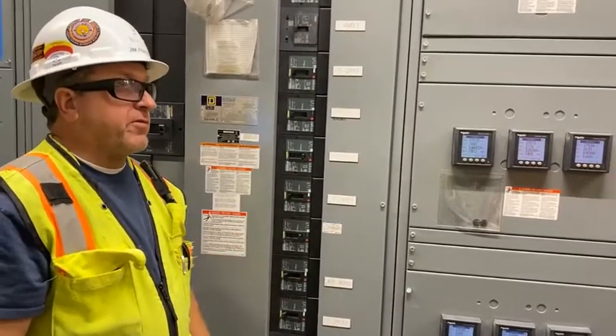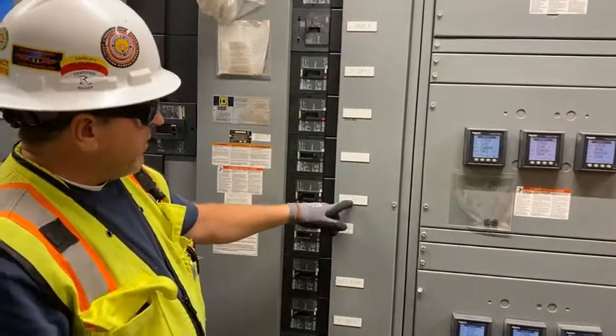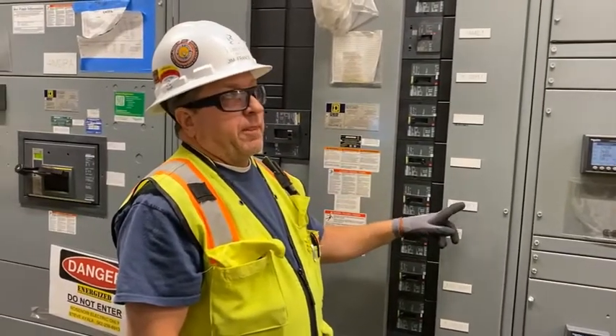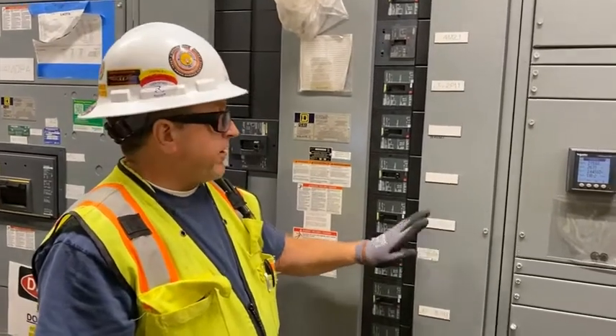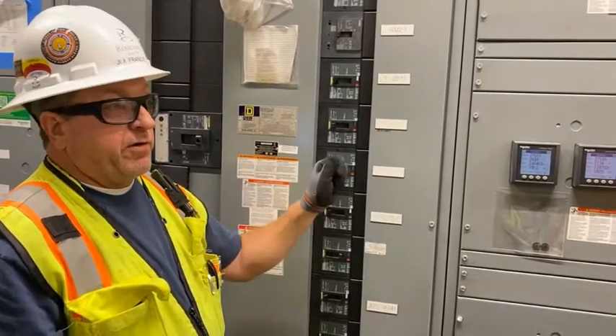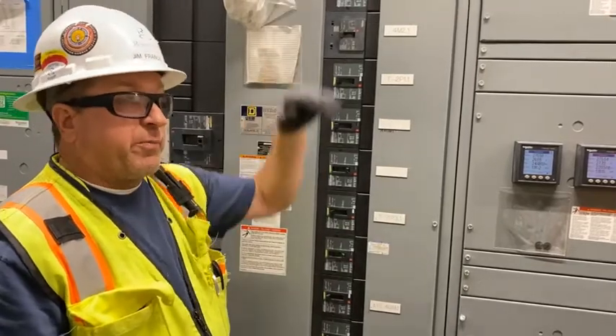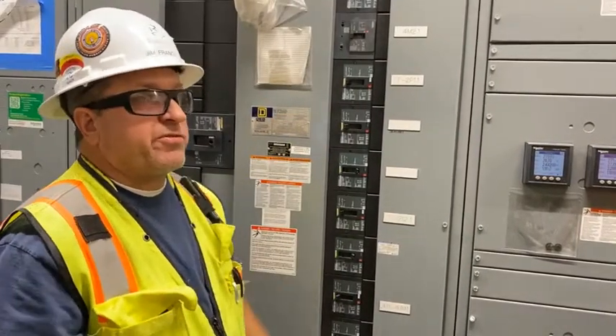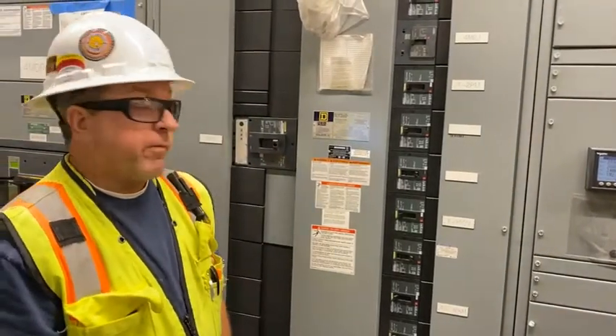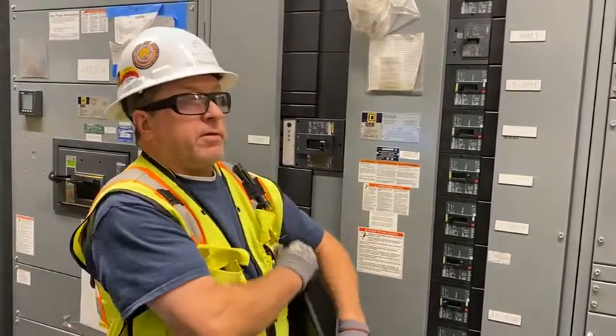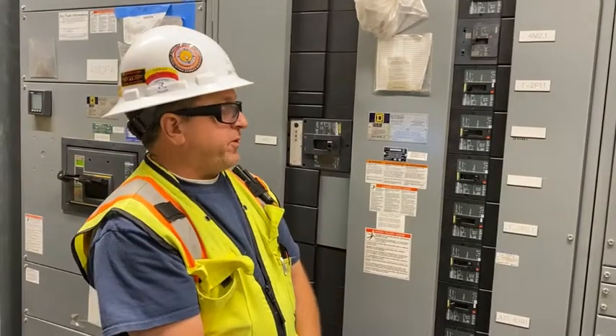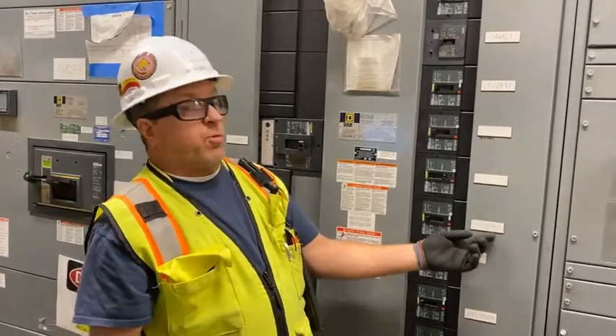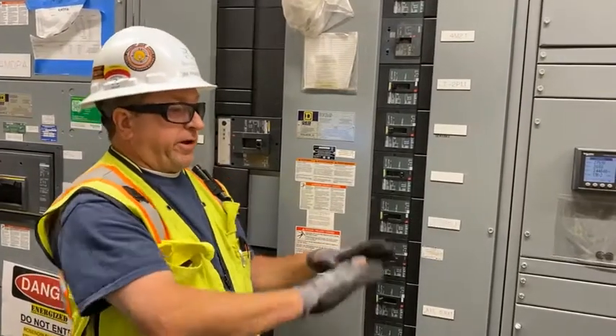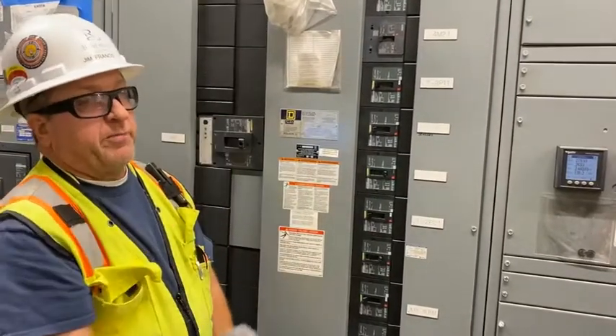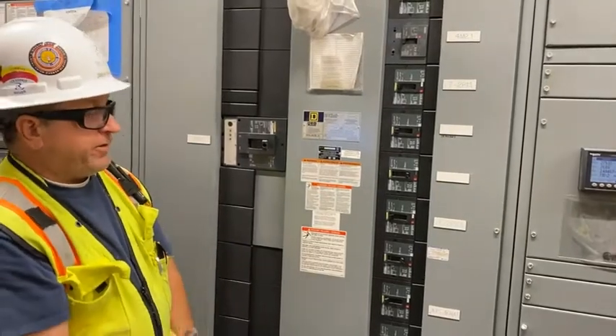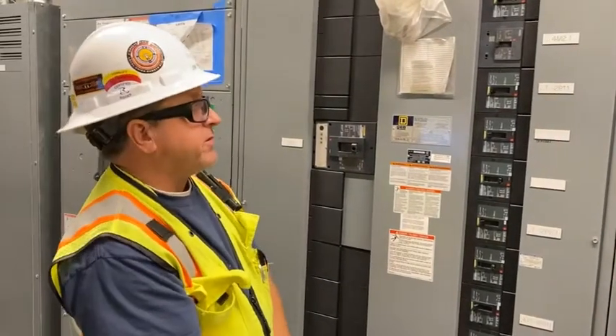All the panels have mains. And then, say if you go up to the second floor, this panel, not the transformer, but the panel after that, will have 3-pole breakers that do different panels upstairs. So it just continues. Oh, I got you. So you should never have to come in and turn anything off, just turn it on upstairs, wherever you're at. For instance, if you need to get up to the 6.1 panel, you'd probably go to the second floor, and the individual breaker for that panel would be on the second floor. You just have to look at the single line diagram for that.